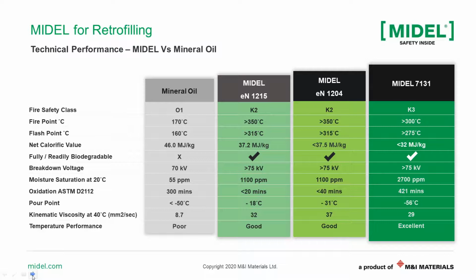The next point, which can sometimes be important, is the moisture saturation of a liquid, like in a very humid environment. In this case, we need a liquid that can absorb and keep a high moisture level. Mineral oil has around 55 ppm maximum water level at 20 degrees C. However, MIDEL EN and MIDEL 7131 have higher numbers: natural ester MIDEL EN has around 1100 ppm, about 20 times higher, and MIDEL 7131, the synthetic ester, has more than 2000 ppm, around 50 times higher.